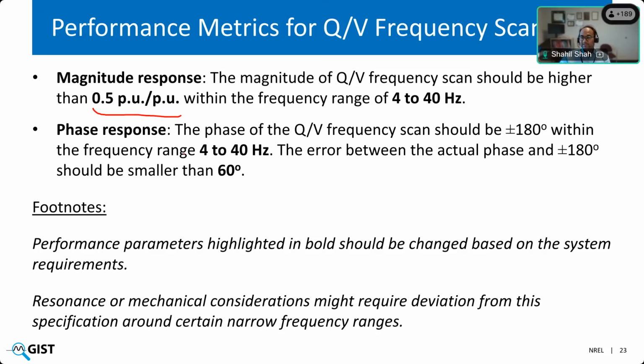And then the phase response should be equal to plus or minus 180 degrees within this frequency range of 4 to 40 hertz. But we are giving the tolerance of 60 degrees. So there can be an error of 60 degrees compared to this. Again, we have kept this tolerance much wider. We would rather have it like 20 or 30 degrees. But if someone is using these metrics without doing any studies, without understanding its impact on the technology, for example, wind plant or PV plant might not be able to provide this response with such tight bands, then we would like these numbers to be more relaxed, the example values more relaxed or less demanding in the report.